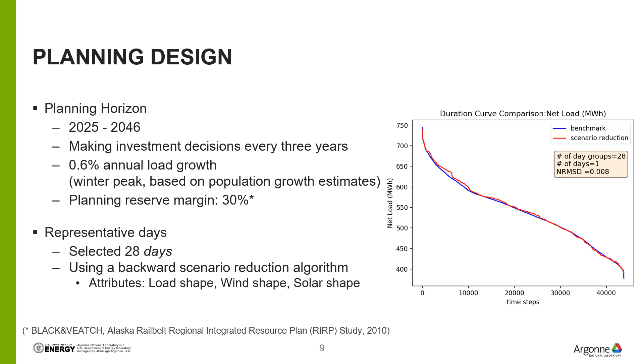In terms of reliability criteria, this is actually important. Typically, we set the operating reserve requirement based on the N-1 criterion. But in this study, instead of N-1, we use N-2, which means we want to make sure that the system is N-1 reliable after losing 2 elements simultaneously. This was recommended by our local advisory board member, and it actually reflects how local utilities operate their system.